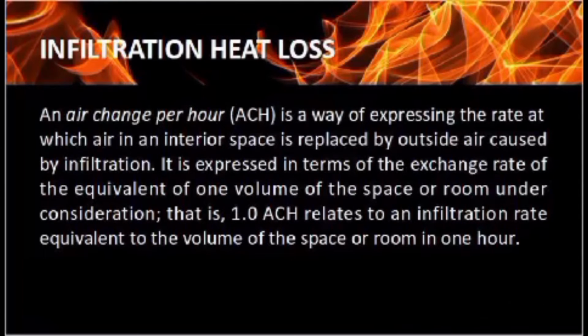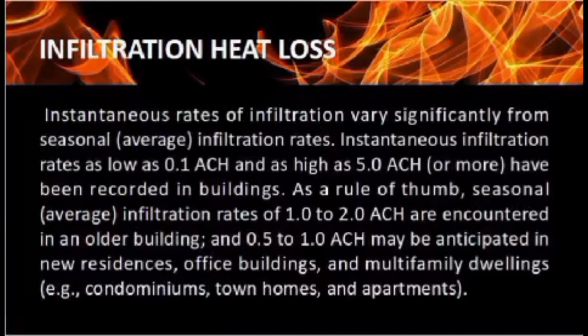Air change per hour is expressed in terms of the exchange rate of the equivalent of one volume of the space or room under consideration. 1 ACH relates to an infiltration rate equivalent to the volume of the space or room in 1 hour. So, pag 2 ACH naman, it means twice na yung volume of the space na na-replace by infiltration. Instantaneous infiltration rate as low as 0.1 ACH and as high as 5 ACH. Infiltration rate of 1 to 2 ACH is usually na-encounter siya sa mga older building, while 0.5 to 1 ACH is sa mga new residences and buildings naman.